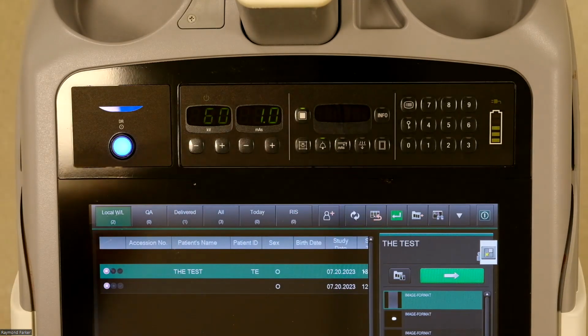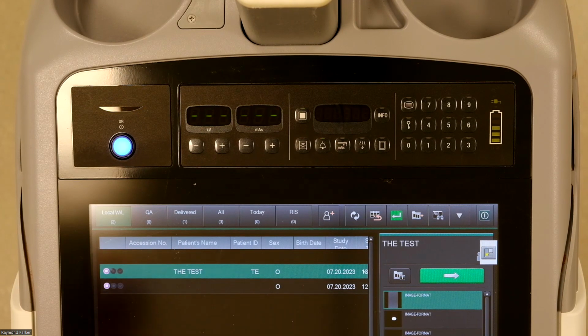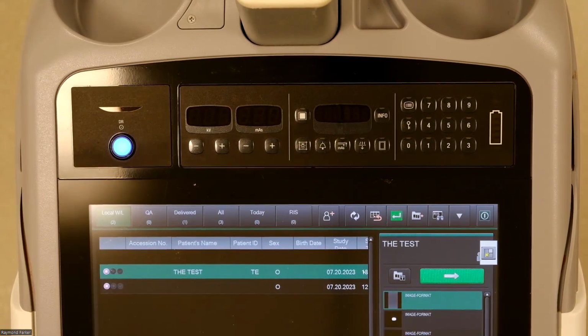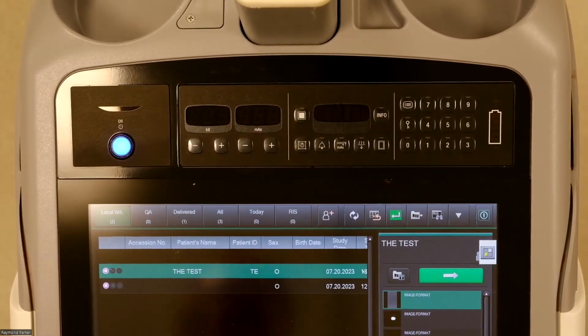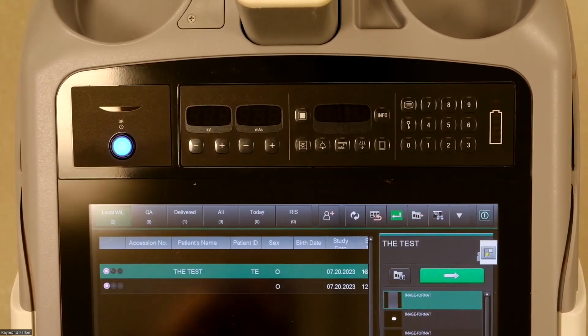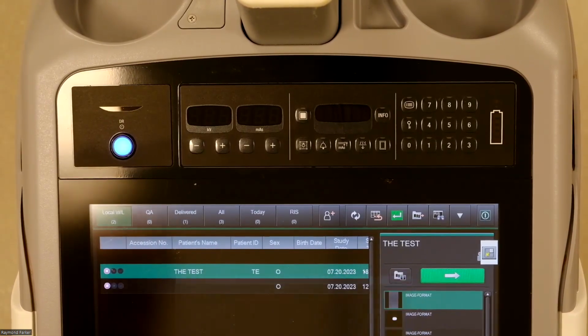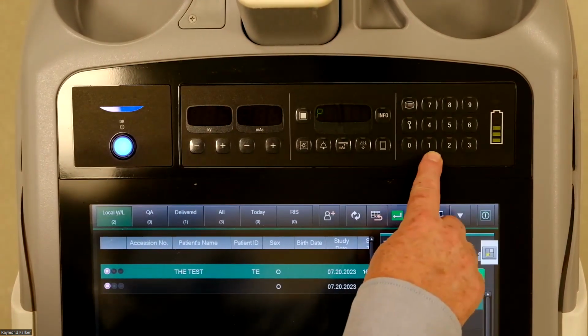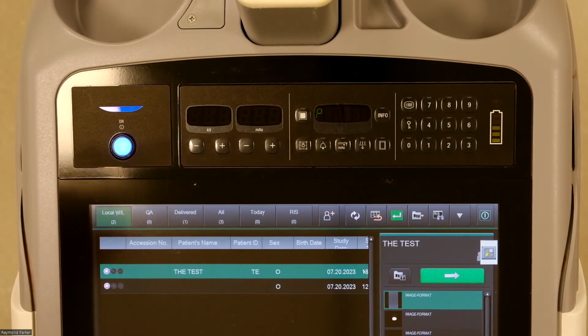I want to go back to the PID. I'm going to turn the unit off for a second or two, and then I'm going to turn the key back on. I want to discuss with you that the PID can actually have an additional value. So once the PID is applied to a unit, putting in a simple user 1, 2, 3, 4 or 4 ones and then hitting the key does not open all of the user settings functions.